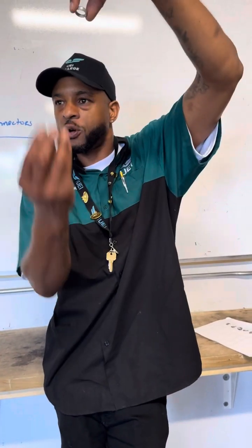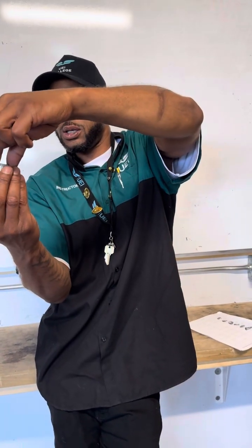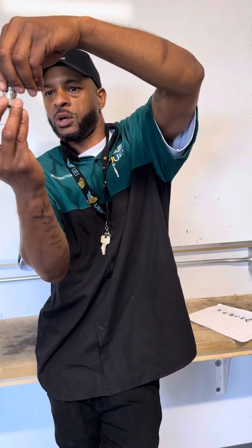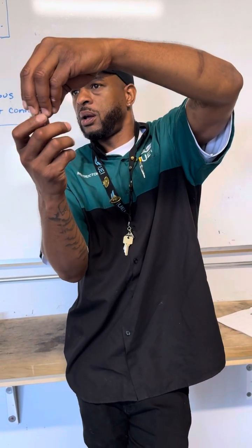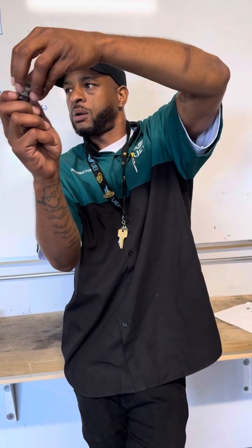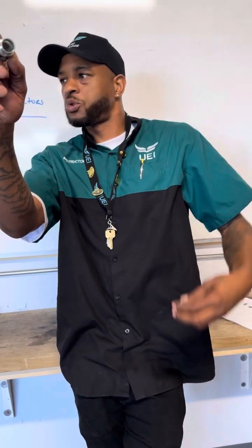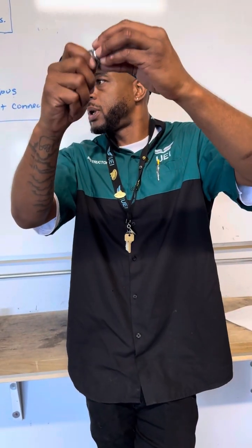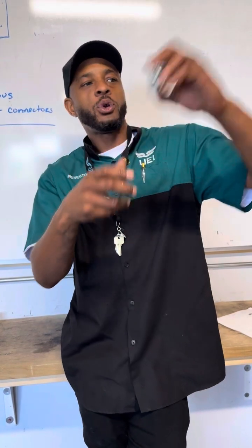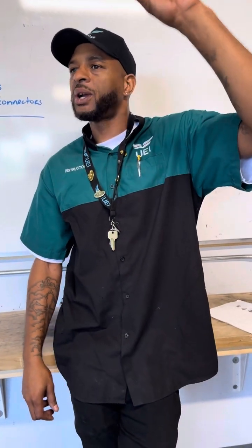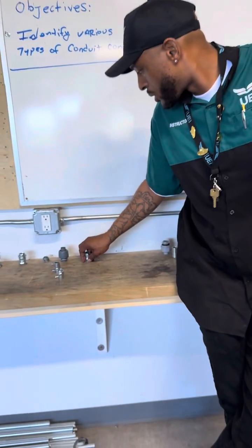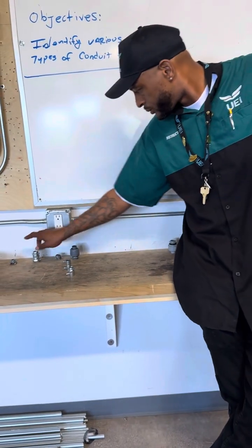Okay, so you put this over the pipe, here and here like this, screw this on, and it locks in. You take your lock ring off, goes inside your 4S box with your box offset, tighten it on, and you're done. Now, if I'm using this compression connector at a 1/2 inch, I will use a compression coupling, which I don't have one up here.